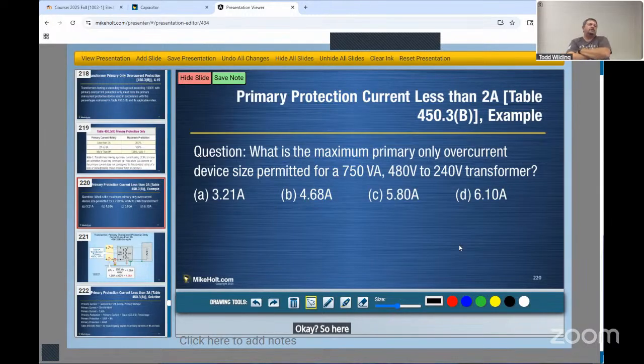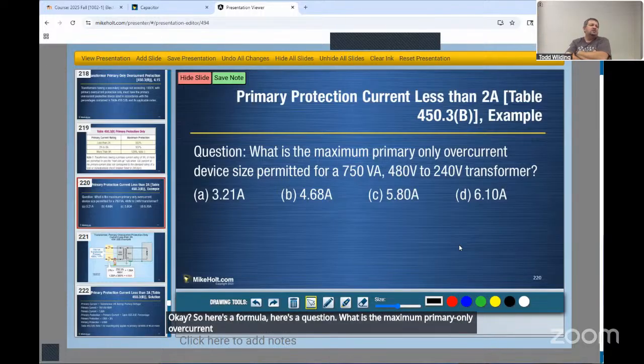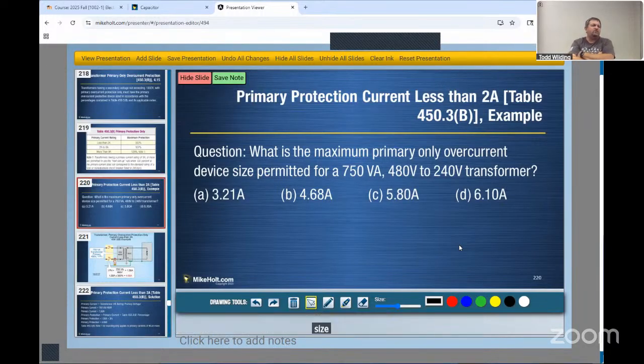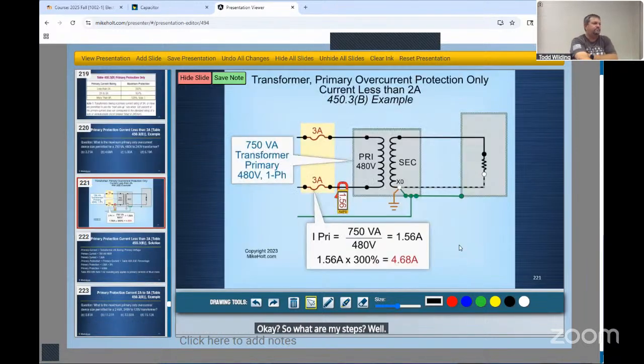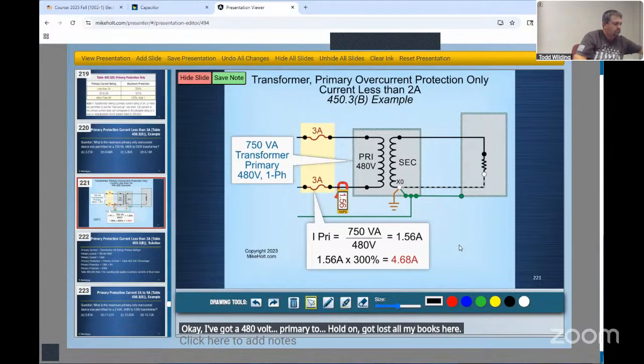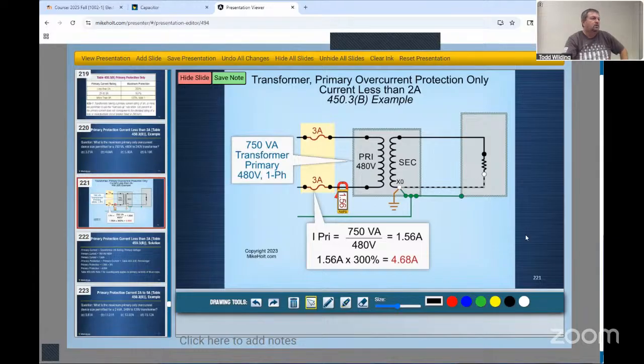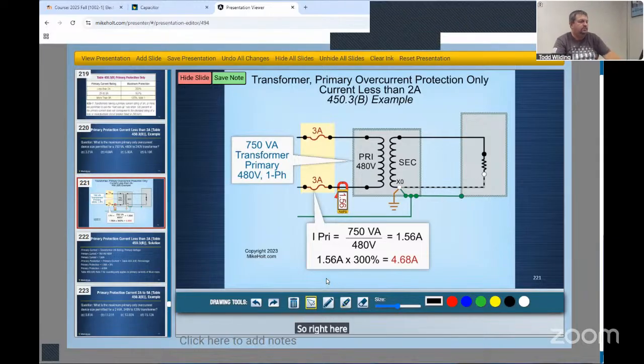So here's a question. What is the maximum primary only overcurrent device size permitted for a 750 volt-amp, 480 to 240 volt transformer? Okay. So what are my steps? Well, let me show you. I've got a 480 volt primary. Hold on, I lost all my books here. So right here, let's go back one.